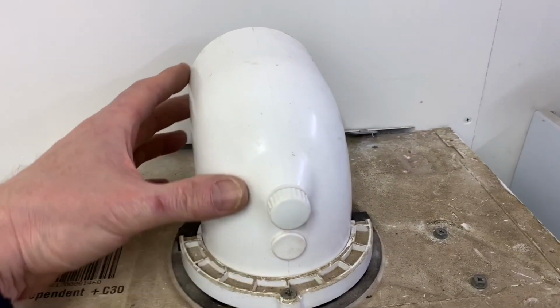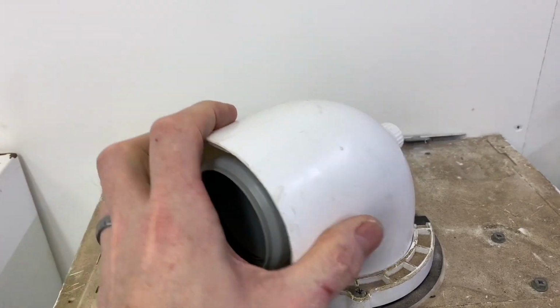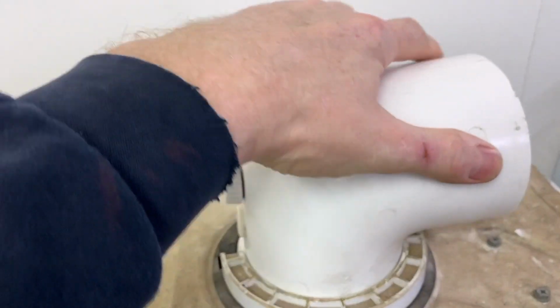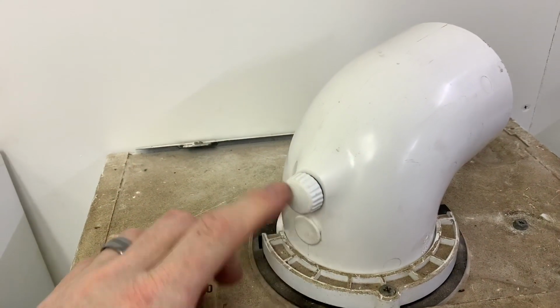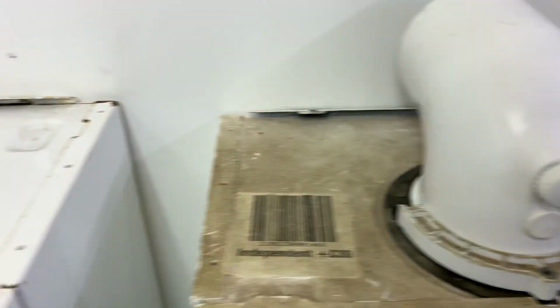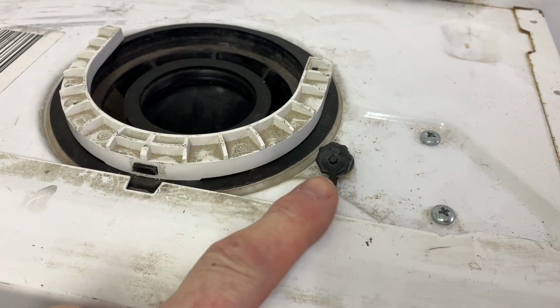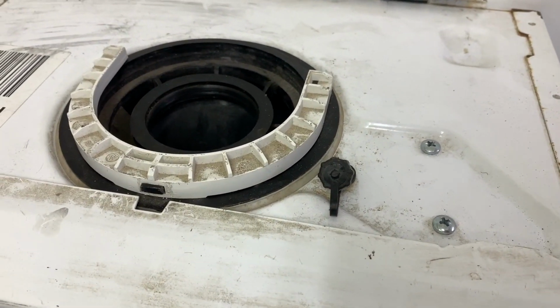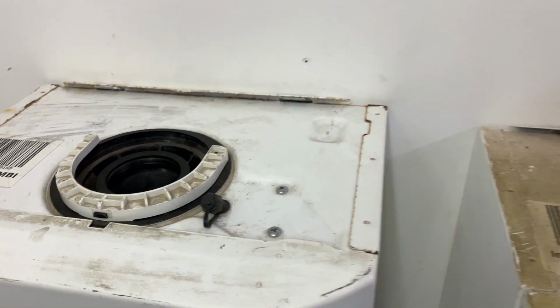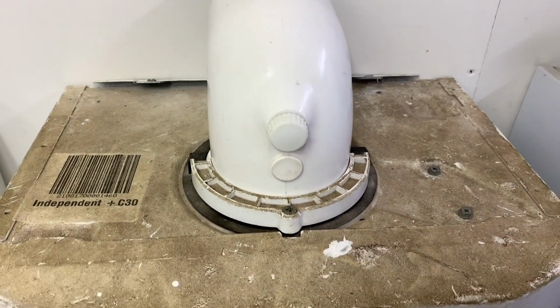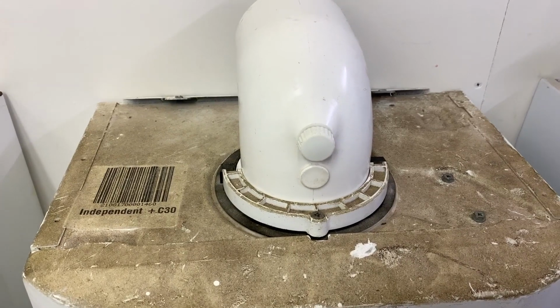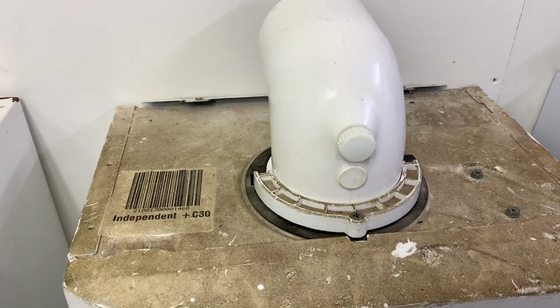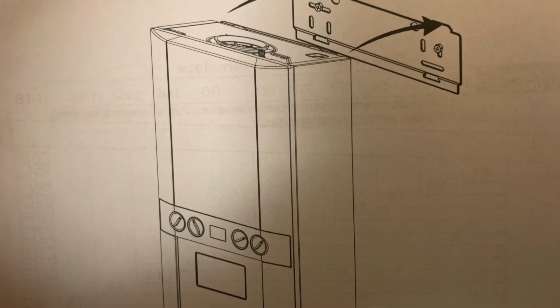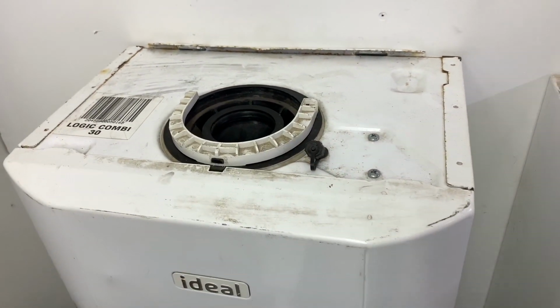Again, the turret can move in any direction, but one thing you've got to be worried about is your sample point. You need that so you can get on it, whereas the older one, you could put them anywhere because you could still get on it. So that's the top of these two Logics. They're pretty much the same as the new one. Bracket's still the same. You can't pipe up the back of these, you need a standoff jig. Even on the new one, you still need a standoff jig.